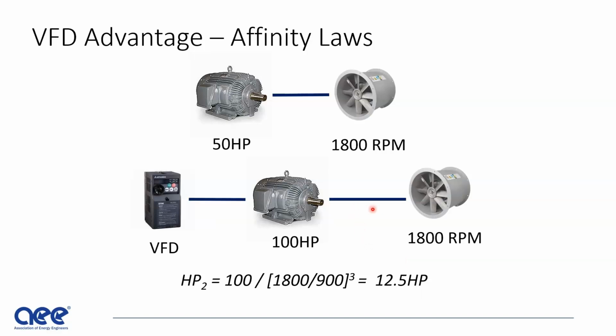So let's look at this example, and this is one that John and I were talking about in prior weeks. You have a 50 horsepower motor running a fan at 1,800 RPM. You put on a VFD with 100 horsepower, and you now reduce the CFM by half because you're reducing the rotation of the motor by half. So instead of operating at 60 hertz, it's operating at 30 hertz on a 100 horsepower motor. Sure, it's only 12.5 horsepower, but look at the difference in the delivered CFM. It's cut in half. So that's what's problematic about this particular arrangement.